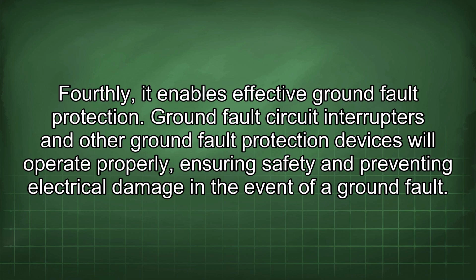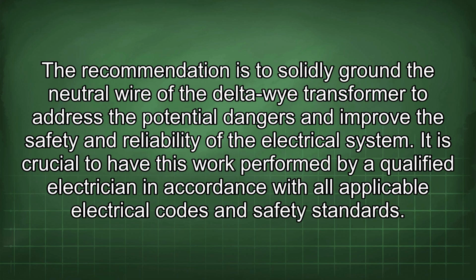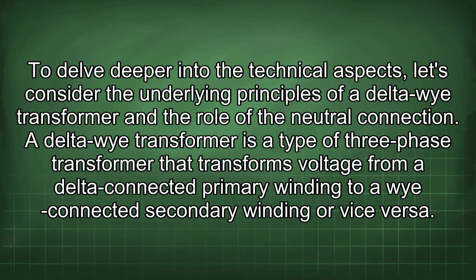Fourthly, it enables effective ground fault protection. Ground fault circuit interrupters and other ground fault protection devices will operate properly, ensuring safety and preventing electrical damage in the event of a ground fault. The recommendation is to solidly ground the neutral wire of the delta-wye transformer to address the potential dangers and improve the safety and reliability of the electrical system. It is crucial to have this work performed by a qualified electrician in accordance with all applicable electrical codes and safety standards. To delve deeper into the technical aspects, let's consider the underlying principles of a delta-wye transformer and the role of the neutral connection.